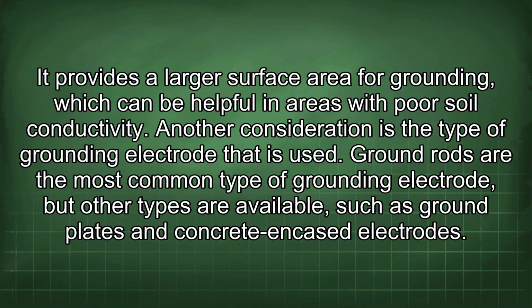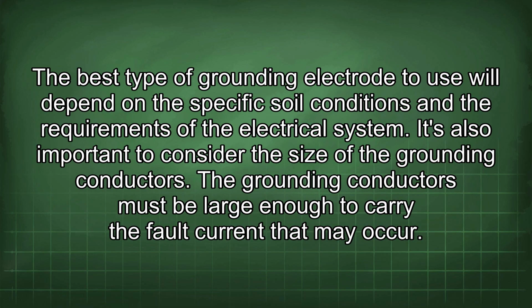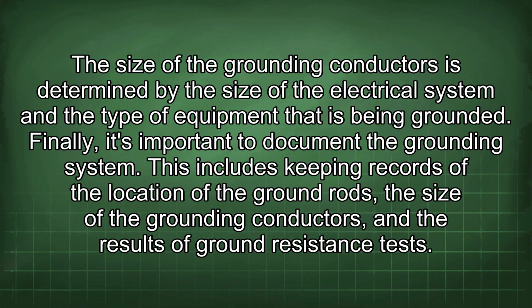Another consideration is the type of grounding electrode that is used. Ground rods are the most common type of grounding electrode, but other types are available, such as ground plates and concrete-encased electrodes. The best type of grounding electrode to use will depend on the specific soil conditions and the requirements of the electrical system. It's also important to consider the size of the grounding conductors. The grounding conductors must be large enough to carry the fault current that may occur. The size of the grounding conductors is determined by the size of the electrical system and the type of equipment that is being grounded.